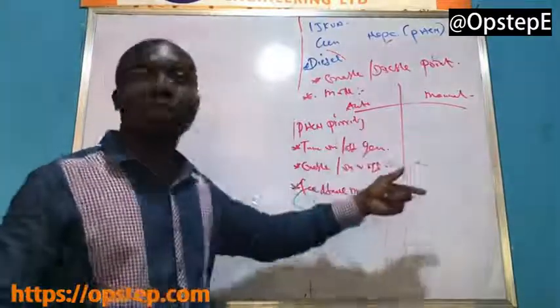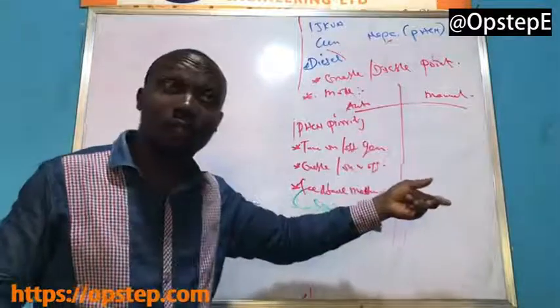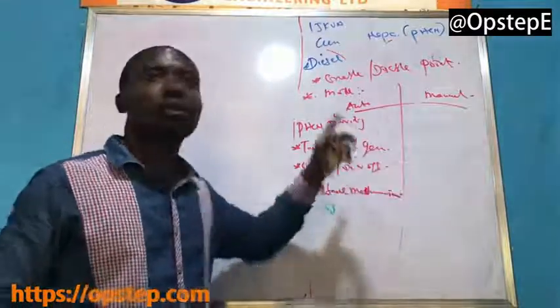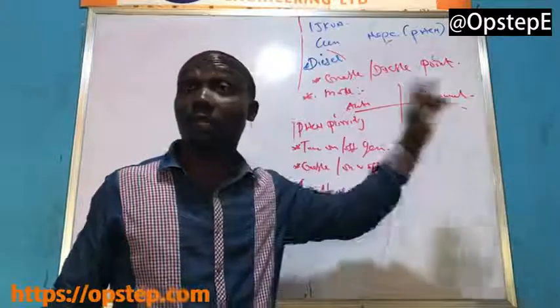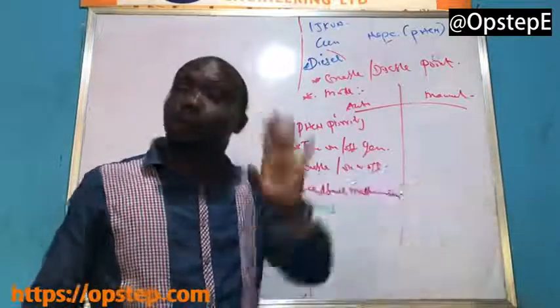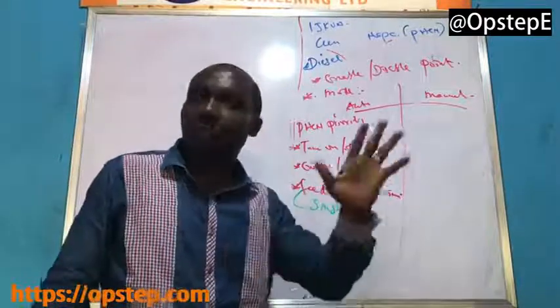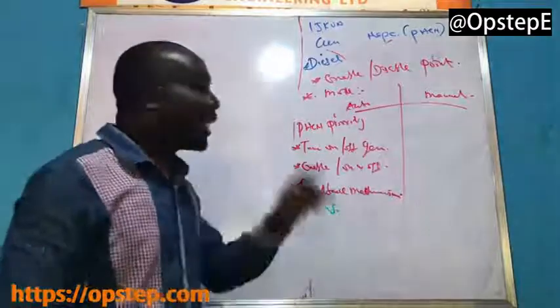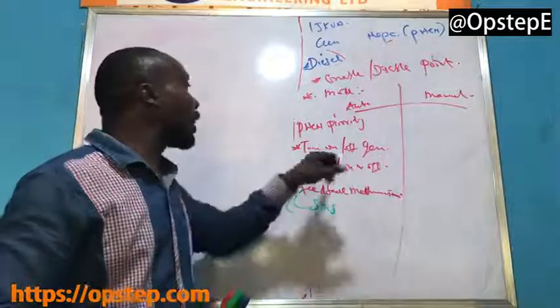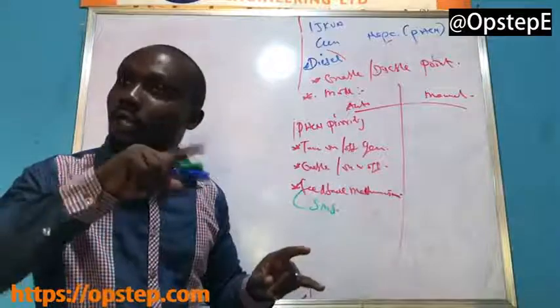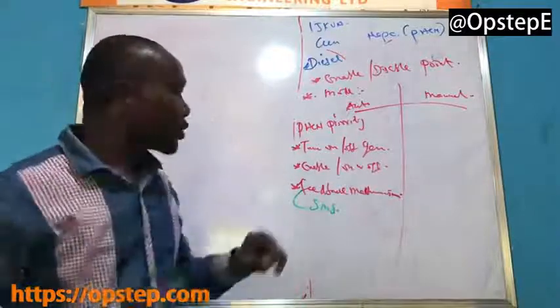And if it tries to turn on the generator and the generator does not come on after 3 trials, it also gives you an SMS feedback message to let you know the generator did not come. So you know exactly what the system is doing at every point in time. Now, let's assume it tries to turn on the generator and it does not start. What can you do? Few things.